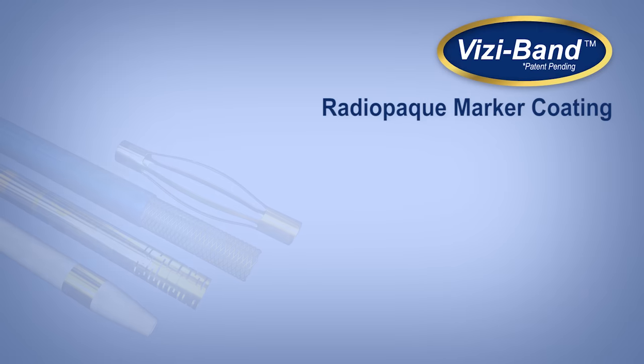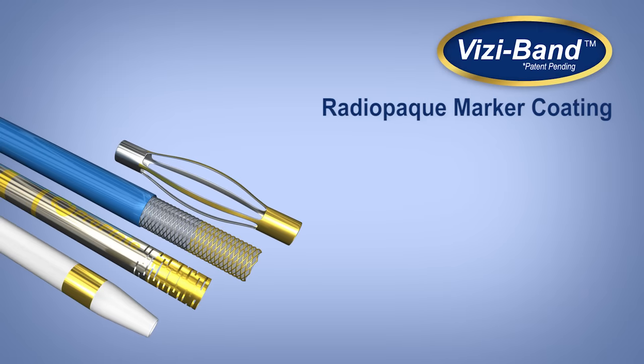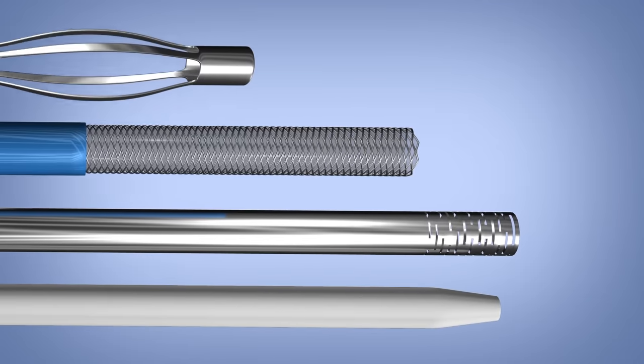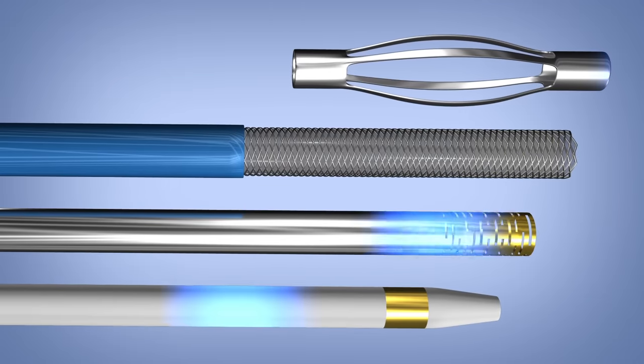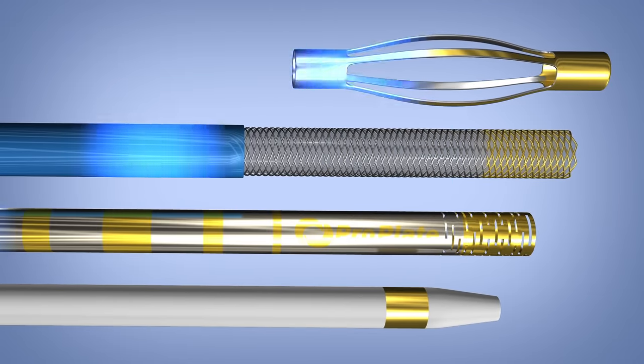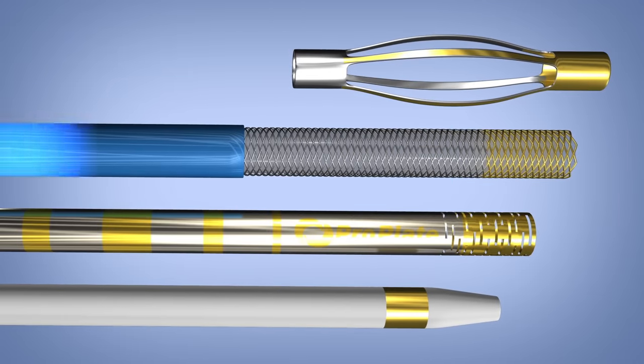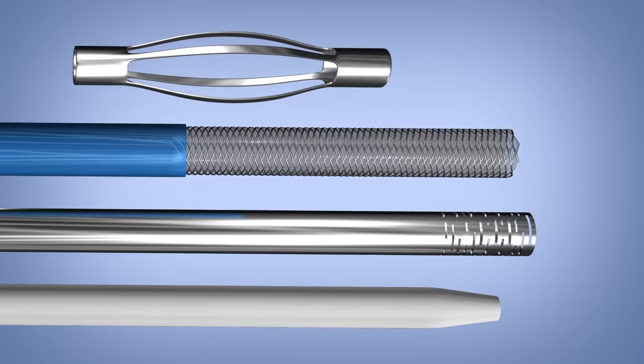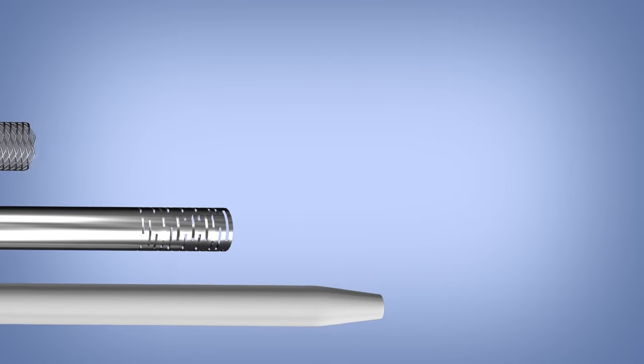Vizi-Band is a radiopaque marker coating innovation that was made available to market in late 2014. It is a proprietary metal coating process that atomically bonds directly to a catheter, guidewire, hypotube, stent, or similar device.